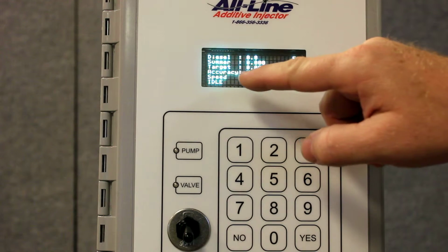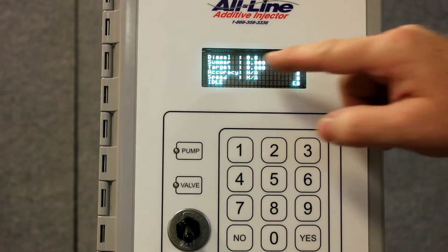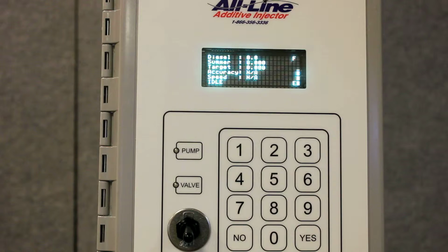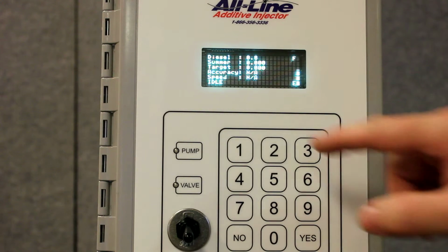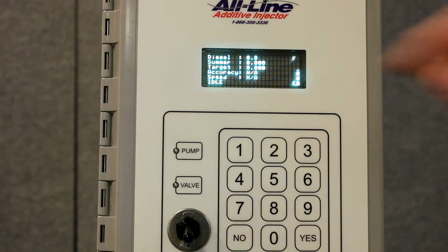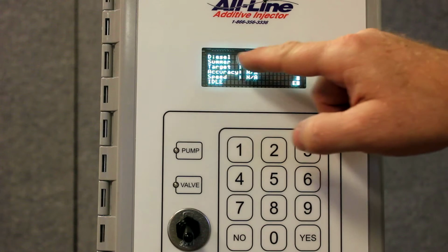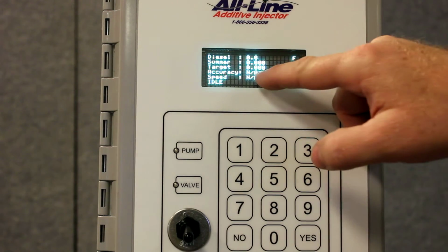So if I've done 1,000 gallons of diesel, the target often will be 1.000 because most additives are 1 to 1,000. The entry that says the additive name hopefully also says 1.000, but it might say something slightly different, 0.985 or 1.004. Those two numbers will be used to calculate the accuracy.